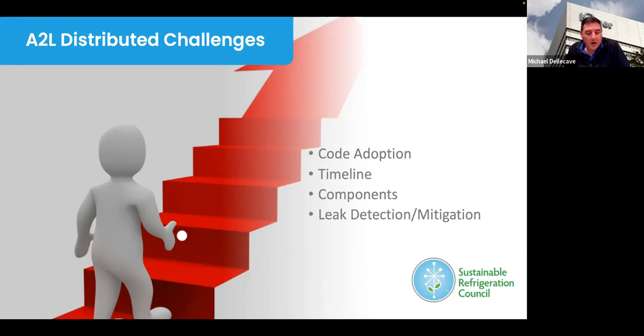Leak detection, again, it is a bonus, but there is a cost to that, a cost up front, and a cost to maintain it for you to get the benefit out of it. The mitigation piece of leak detection is another cost. Each case will need isolation valves in the event of a leak, to prevent that leaking refrigerant from coming out of the system beyond what's in the case. This will pose new challenges. Not only will we have to maintain it, but the store personnel will have to understand what's going on and how to react to this micro detection of leaks. That's something the industry really hasn't dealt with yet.